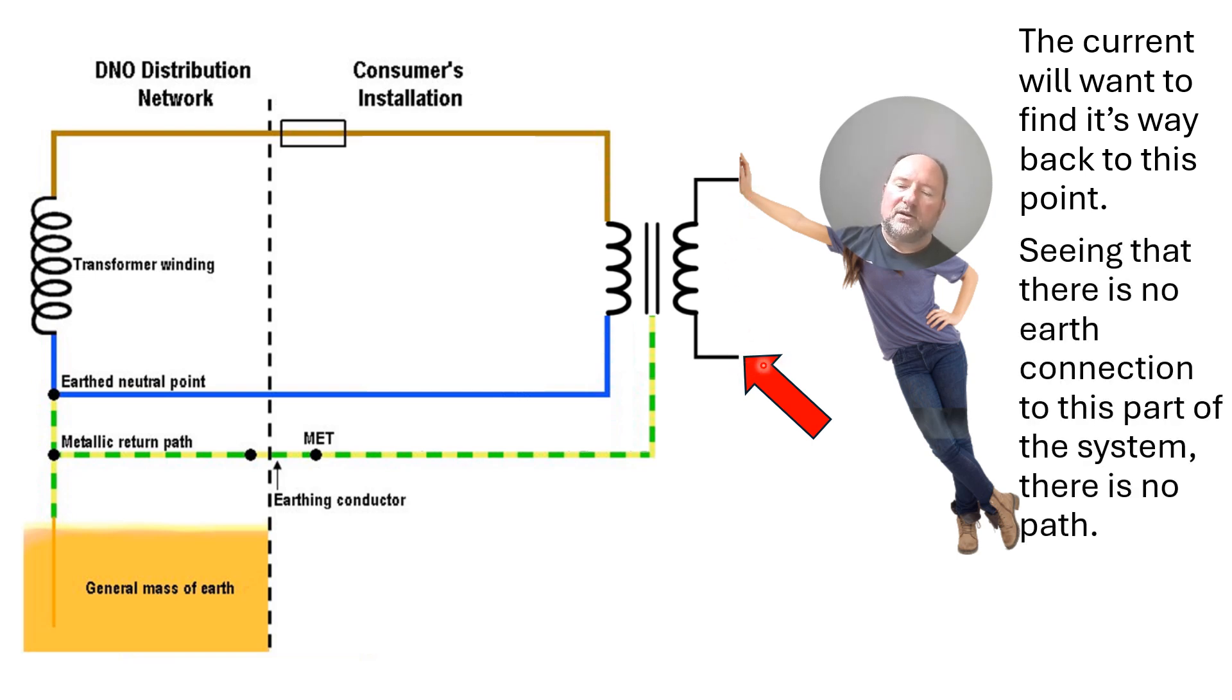Now, seeing that this secondary part here has absolutely no connection to Earth, then the current cannot find its way through the general mass of Earth back to this point. And since then there's no path for the current to take, then there is reduced risk of shock.